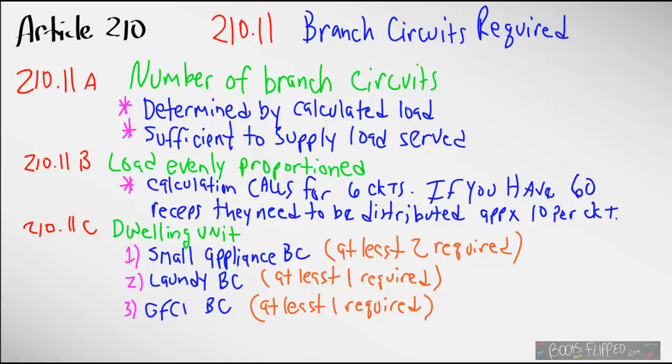We also have requirements in a dwelling unit that require us to, in 210.11C1, we have to have at least two small appliance branch circuits, and those are going to serve our countertops. And there are other places that those can serve besides the counter, and we will get into that later on in class. We also have to have a laundry branch circuit, and there's only one of those required, at least one. And then we have to have a GFCI branch circuit for our bathrooms. There's at least one of those required as well.